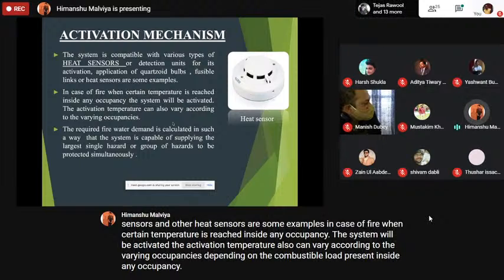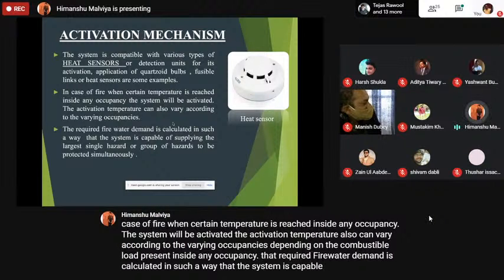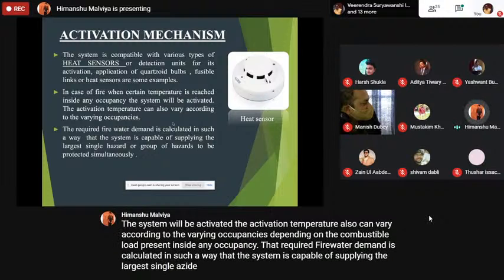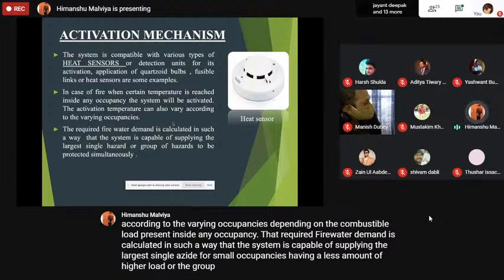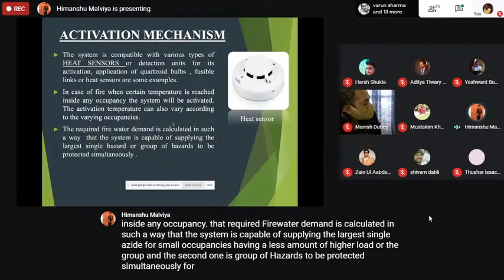The required fire water demand is calculated in such a way that the system is capable of supplying the largest single hazard for small occupancies having a small amount of fire load, and the second one is a group of hazards to be protected simultaneously for those occupancies having a much higher fire load. This is how the system will look in a working situation.